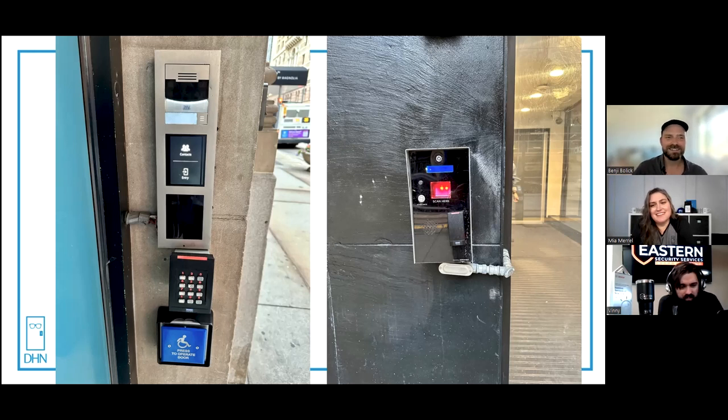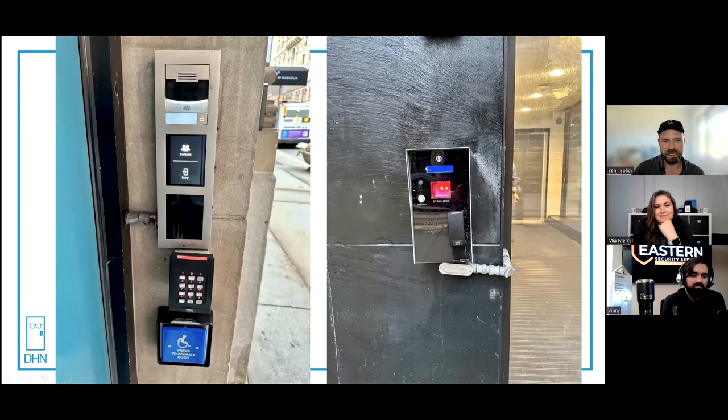I don't see anything actually securing any of that to the wall, unless it's around the corner. I don't see a strap, unless they put one in the LB there, probably a sheetrock screw somehow. There could be some kind of tie down right there. Is that what you were talking about? Yeah, around the corner there could be something, but I don't see anything even really holding that there.